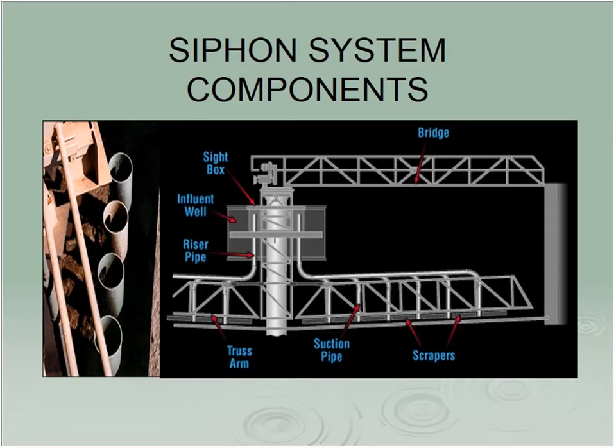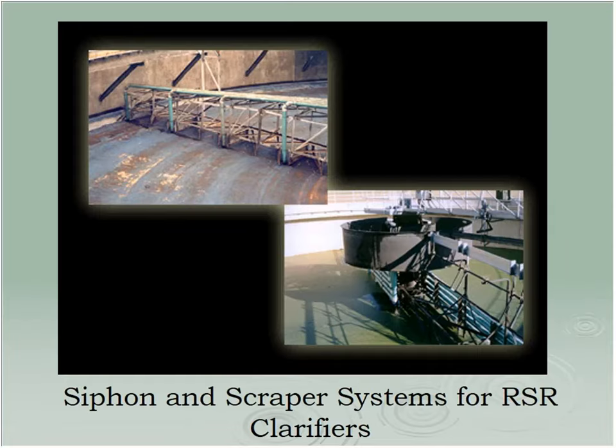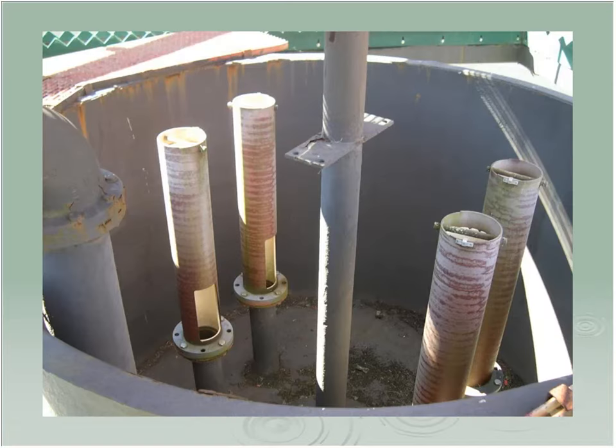So as this slowly plows around, it's pushing material towards these pipes. And if we get the pipes on the left-hand side inside that box, see the piping arrangement on the rake mechanism. Here we go. Inside that box, you see there's an opening from that pipe. This opening is below the operating level of the clarifier itself, so now I've got a hydraulic gradient, and the water wants to flow downhill. So as the water flows, it easily picks up the solids off the bottom and carries them with it up into this box. And it's a pipe that takes this off to be handled later on.